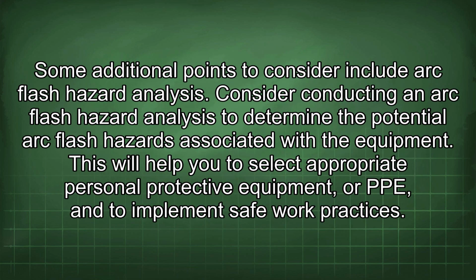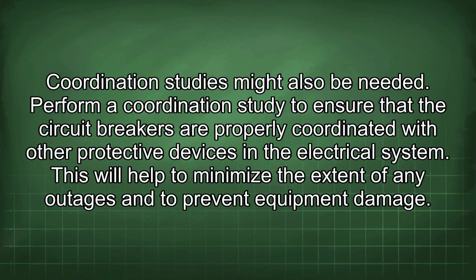Some additional points to consider include arc flash hazard analysis. Consider conducting an arc flash hazard analysis to determine the potential arc flash hazards associated with the equipment. This will help you to select appropriate personal protective equipment, or PPE, and to implement safe work practices. Coordination studies might also be needed. Perform a coordination study to ensure that the circuit breakers are properly coordinated with other protective devices in the electrical system. This will help to minimize the extent of any outages and to prevent equipment damage.